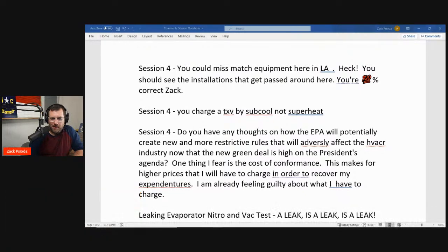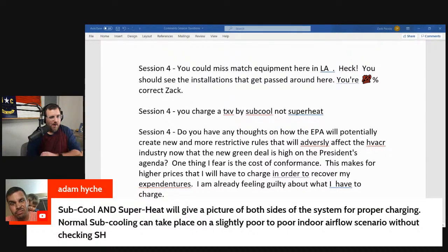All right, I'm going to bring this back up. Adam says subcool and superheat will give a picture of both sides of the system for proper charging. Normal subcooling can take place on a slightly poor indoor airflow scenario without checking superheat. Yeah, you can have some variables. If you don't check both of them, you're not getting the whole story, basically.